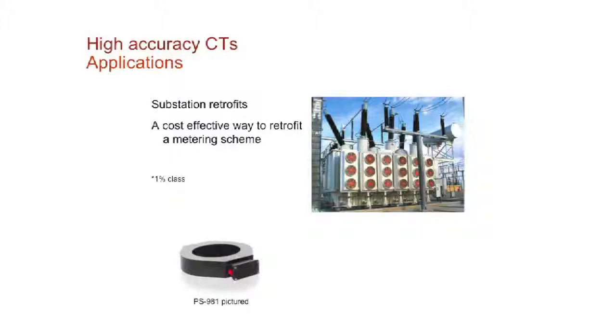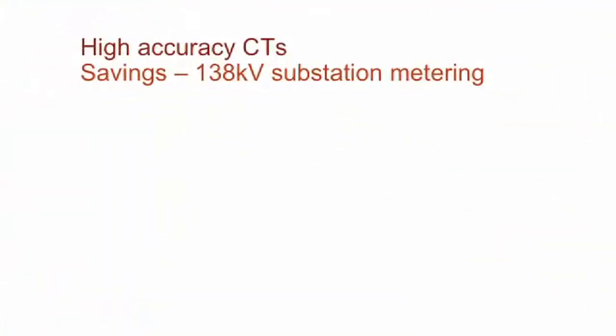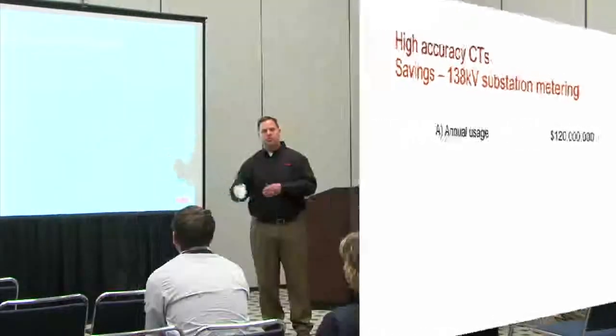Okay? Oftentimes, a power transformer like you see here will have, say, a relay protection class CT inside when it was first built, but maybe the utility later on wants to add some metering at the substation. These are easily installed over the bushings, and you can not purchase a high voltage instrument transformer, but rather one of these here, and get pretty much the same accuracy that you will with a high voltage instrument transformer for a whole lot less money. Annual usage that might pass through a 138 kV substation, about $120 million a year. That'd be a tie point usually between transmission going down to distribution.